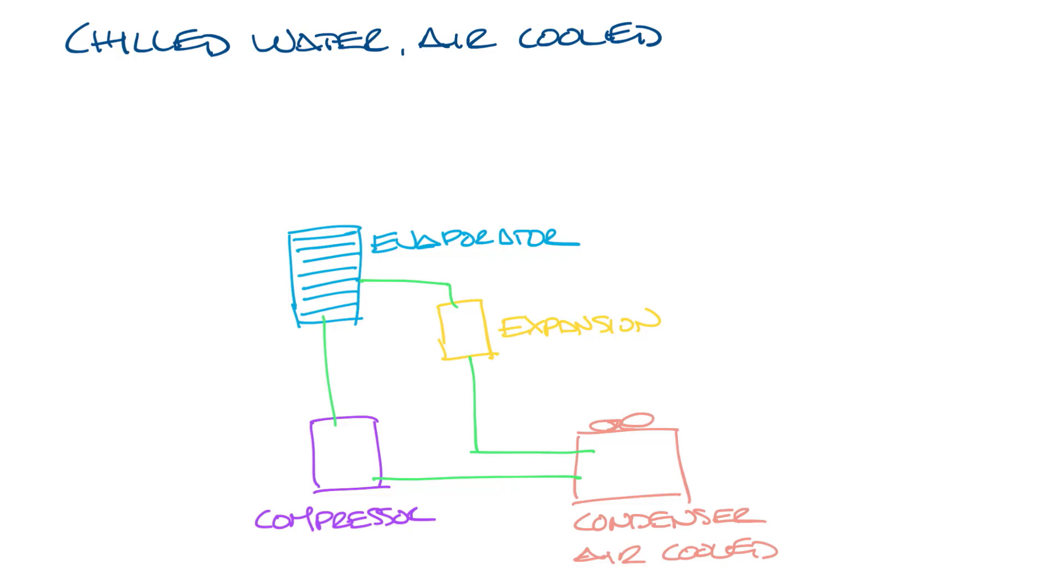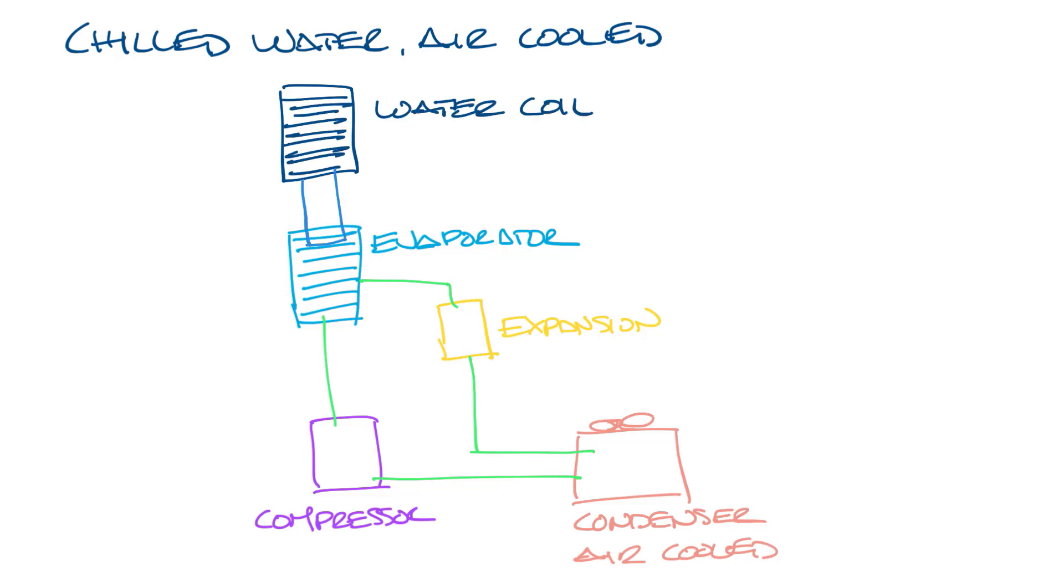But instead of the evaporator cooling down the supply air, it cools down water, which is then sent to a cooling coil, which cools down the supply air. The supply air transfers its heat to the cooling coil, which warms up the water, and the water travels back to the evaporator to be cooled down again.